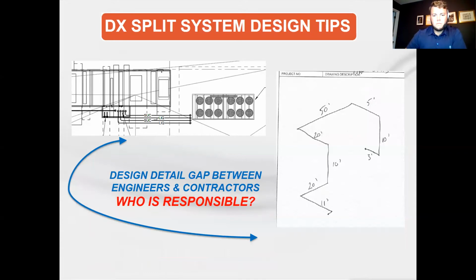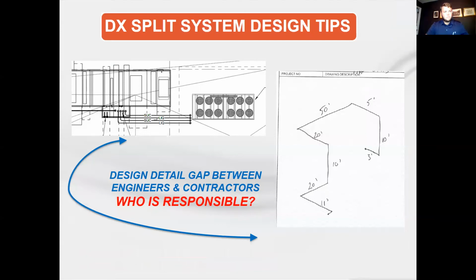So now we'll look at some real world examples here. These are actual drawings that we've used on projects. The one on the left here is the actual refrigeration piping plan that was on the drawings for that first 120-ton system I showed you. You can see that it shows that 4 pipes are required, but it doesn't tell you what the size is. There's probably a note in the schedule that says that the contractor is supposed to size this per the manufacturer's recommendations.